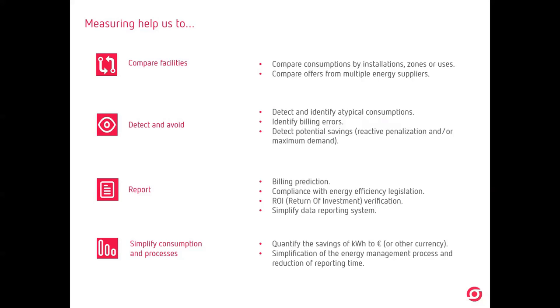We are also able to identify billing errors. We can compare the utility billing meter with our measurements and see if there is any difference with the bill or not. And we are able to detect potential savings and reactive penalization, okay? If we have to pay penalties for reactive energy or maximum demand penalties, okay? If we are exceeding the maximum demand or if we are consuming reactive energy, okay? Then we are simplifying the reporting system. Now we have the billing prediction. We know how we are consuming, okay?